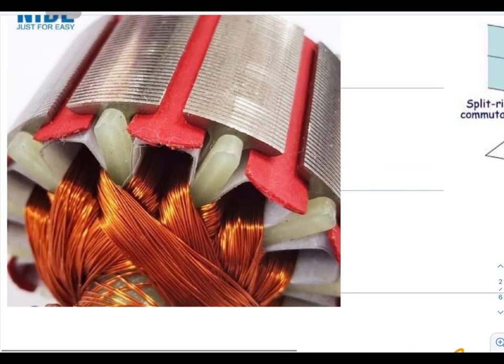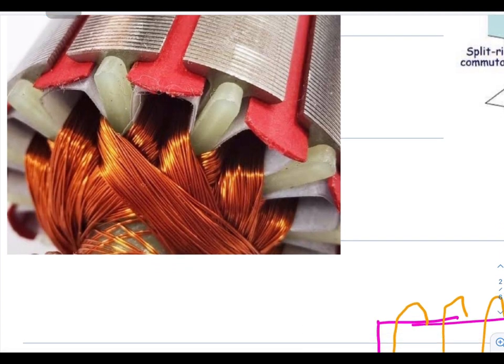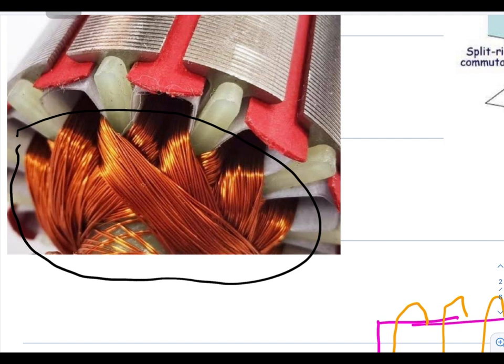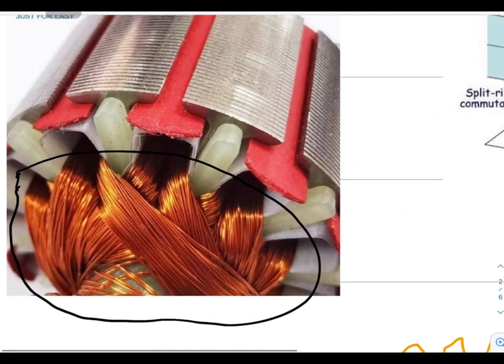Okay guys, the last thing we will talk about today is the armature conductors. The armature conductors are made out of magnetic wire. Even though it may appear to be a wire that is not insulated, it is insulated by a coating, but this coating is transparent. Hence you would think that this wiring is not insulated. These are your armature conductors, and each of them connects to its copper segments. The armature also has armature slots, into which you fit the armature conductors.